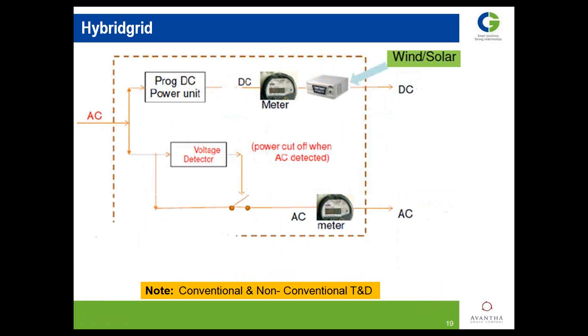Is it a hybrid grid? It is a new area. People have started talking about blackout and brownout and all sorts of things. If you look today in India, in most of the cities, as Pannala also highlighted, Delhi had 15 days of no power. In most of the small cities in India, people are more and more familiar with UPS and storage and all sorts of things. Look at the efficiency of a storage system: getting power from the grid, storing it, and feeding it back to the load. Overall efficiency of the system suffers. Why should I reduce the efficiency of my generated power just by storing, de-storing, and putting it to the load?